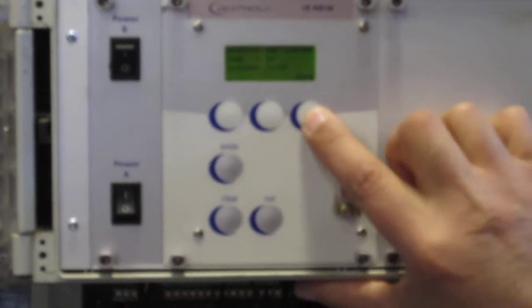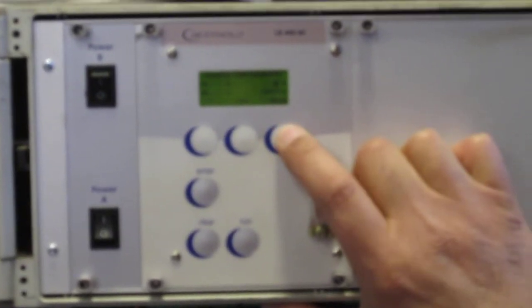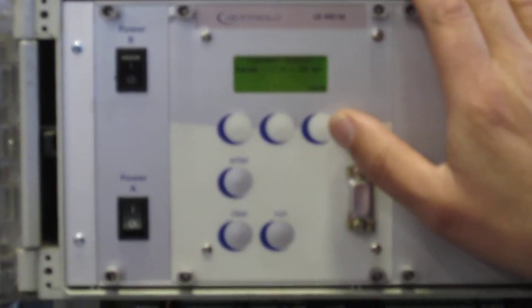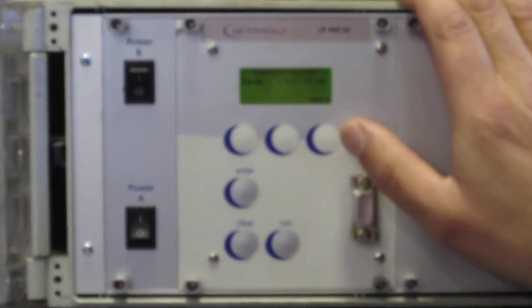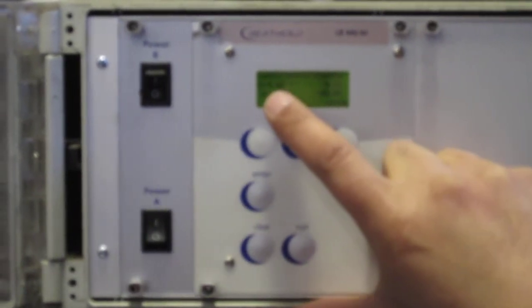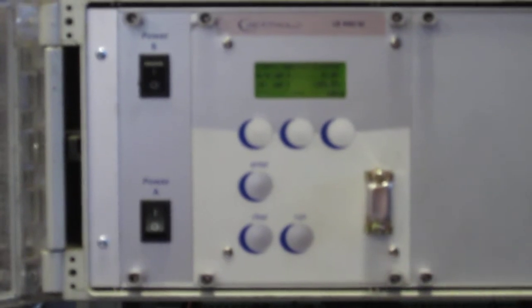So we'll go into measuring parameters. That's what we just went through, and you see we're still on all the same numbers we had, except we did change the source decay, or source replacement date. Output parameters, this is where you set your outputs, and we do a 0 to 20 or 4 to 20. 0 to 20 for European, 4 to 20 for US usually. You all are using a 4 to 20. We just set it to 4 to 20 with this button, say enter, it holds it. And then your output for your 4 is 0%, your 20 milliamps is 100%. So if you're reading 50%, you should have 12 milliamps. It's just a 4 to 20.